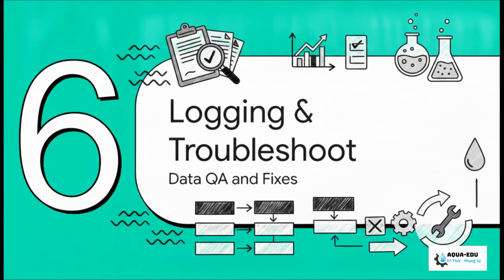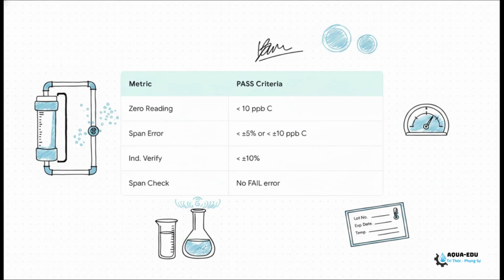And finally, Section 6, Logging and Troubleshooting. We have to document all our hard work meticulously for quality assurance, and of course, know exactly how to troubleshoot if we happen to fail the criteria. These strict pass parameters have to be logged exactly on your physical calibration form. Your zero reading must be less than 10 ppb. The span error needs to be less than plus or minus 5% or 10 ppb, whichever is greater, and your independent verification needs to be within 10%.